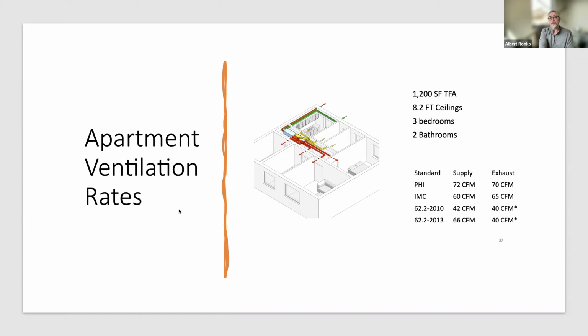International Mechanical Code would give us a different number. 62.2-2010 would give us a different number. 62.2-2013 would give us a different number, and we'll probably get a different number again here as the code cycles change. In any case, we would look at the set of conditions and pick a number. If we're doing single family in California and it's 1,500 square feet with a couple of bedrooms, it's going to be in that 60 CFM range. There's a chart, we look at it, we choose the settings based on the condition of the building and what we think the occupancy is going to be.